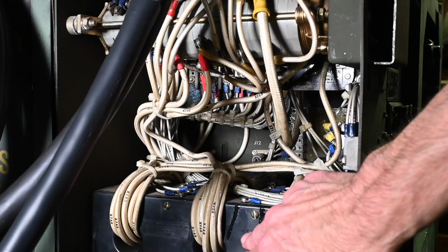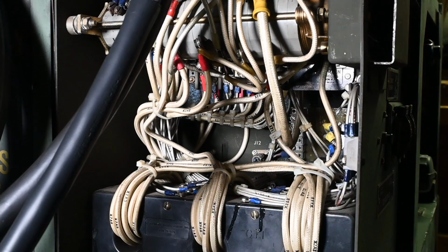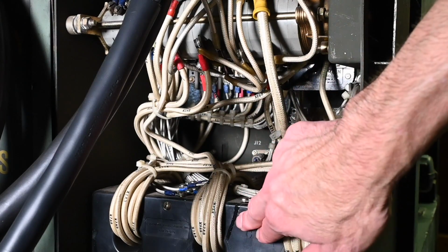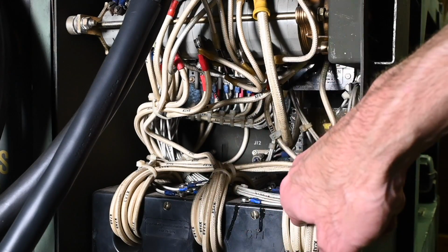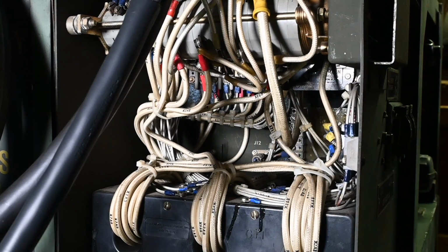So CT1 has nothing to do with the actual voltage regulation of the generator set. It's only for the instrumentation and for the circuit breaker and protection. But on the back side, there's another device that looks similar to this front right here. It has the 3 windows. These wires are passing through it. It has terminals on the top with a number of different wires connected. And that is part of the voltage regulation circuit. And it's a very unusual device.